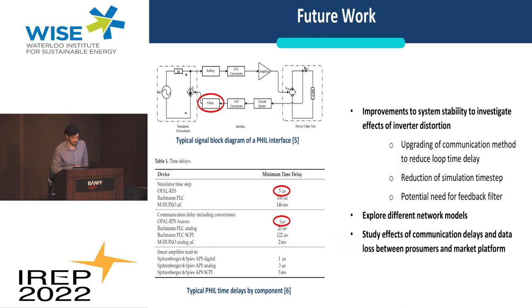The first thing we can do is update the communication method between the power amplifier and the RTDS to use a fiber optic cable instead of just a regular analog connection. That will reduce the time delay for that component from about 20 microseconds to 1 microsecond, so that's a big difference.